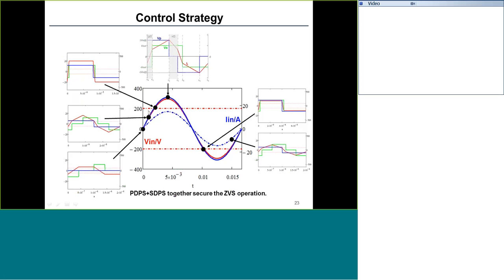When the voltage is lower than the battery voltage, we use secondary side phase shift control. When these two voltages have the crossing point and are exactly equal, the control strategy evolves to single phase shift control. When the input voltage is higher than the output voltage, we change to primary side phase shift control. It looks complex because you have different modes to implement, but in the experiment we can verify it naturally switches from one mode to the other. Only by doing this could we secure soft switching for all switches.